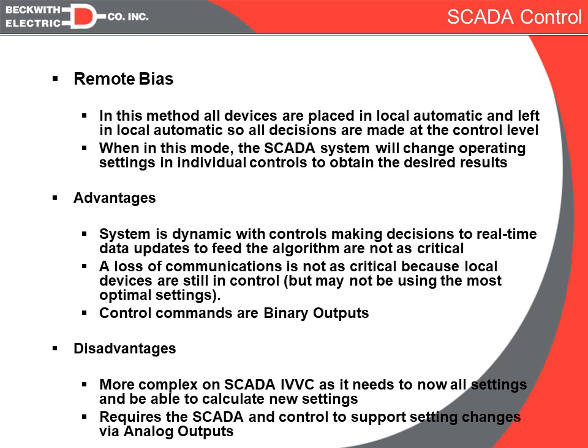So even if we were to lose SCADA communications, our controls are still going to be functioning. They may not have the most optimal settings as the load conditions change on the system, but at least they still are in automatic mode and we do have some sort of operation.